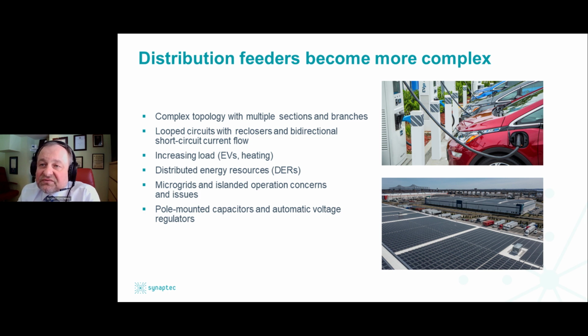They become more complex, with complex topologies with multiple sections and branches. For better availability of power, we tend to use looped circuits with ties closed. So we have bidirectional short circuit current flow. We have reclosers in order to separate the feeder and provide more selective tripping. Loads are increasing. There are distributed energy resources added, and they are not synchronous generators, as you know. They are typically solar, and they are power electronics based, so they have an unusual fault current response. That leads to the issue of microgrids, either preventing microgrids from forming or protecting and monitoring them.